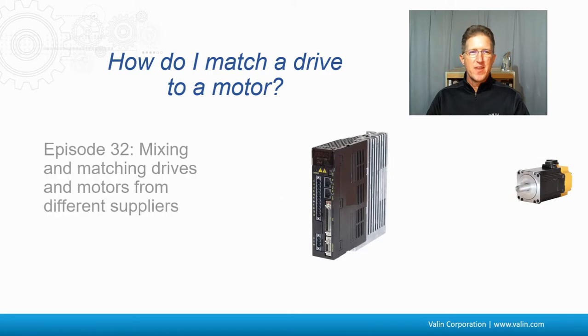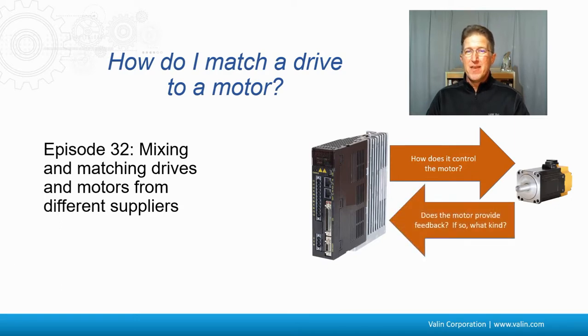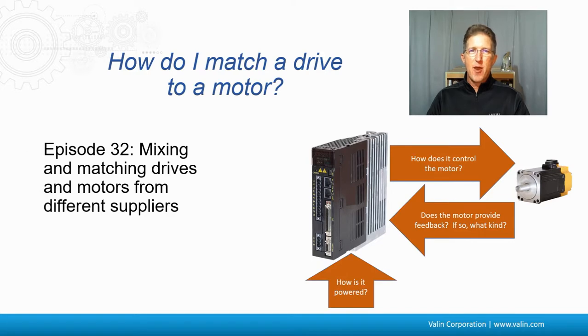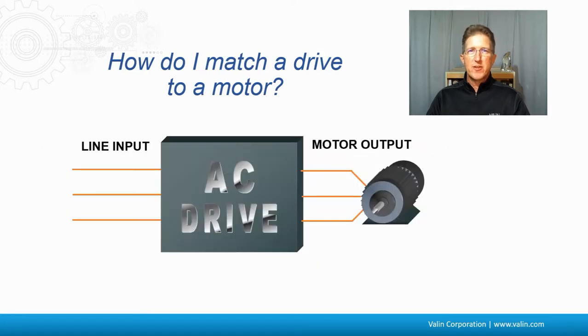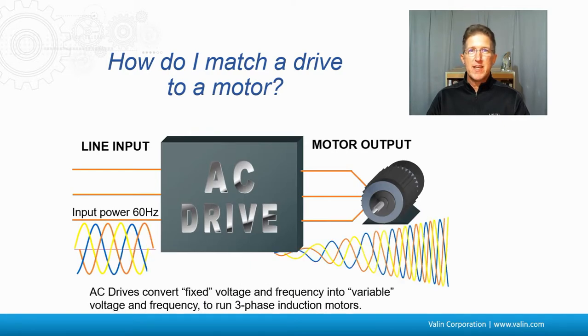I touched base on a lot of this in episode 32, discussing the mixing and matching of drives and motors from different suppliers. A couple reminders: how does that drive control the motor? You have to make sure it's the same technology. And how does the motor provide feedback — and if so, what kind? Again, you need to make sure they have the same technology and talk the same language. One other thing to consider is how it is powered. There are AC drives that take a regular frequency and amplitude of power in and change that to a variable frequency and voltage for three-phase induction motors.